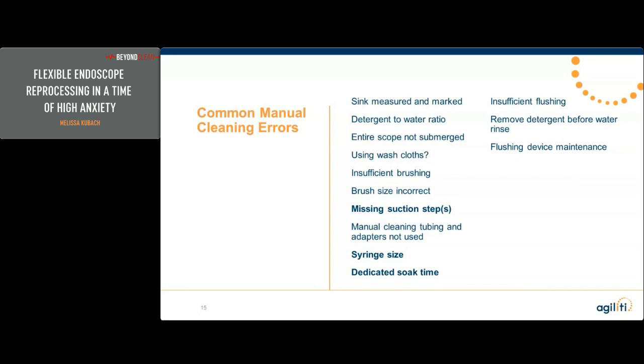So if you can use an automated flushing device, that would be a wonderful thing. Also, a lot of people do not understand where that dedicated soak time comes in. It does not actually start when you put the endoscope into the detergent or enzymatic detergent. It starts after you have done all of the scrubbing, all of the brushing, all of the suctioning, and all of the flushing, and the channels are sated.